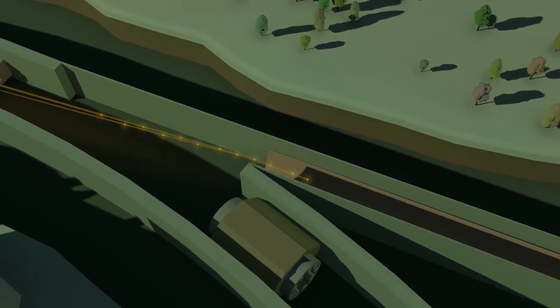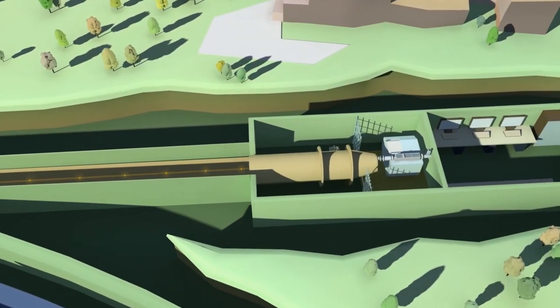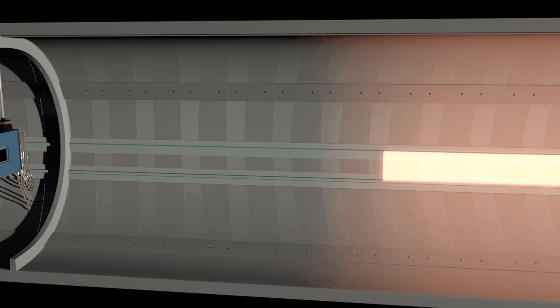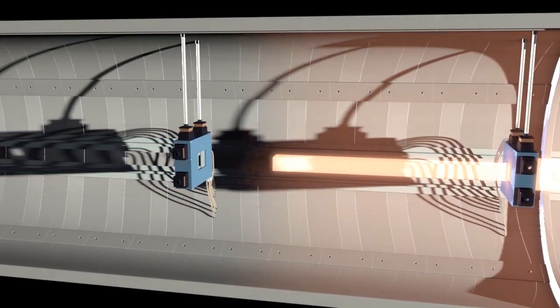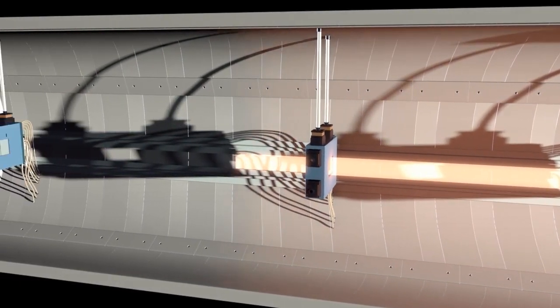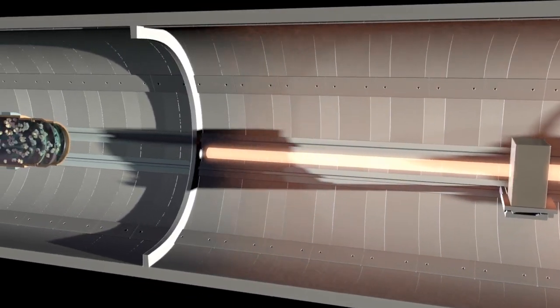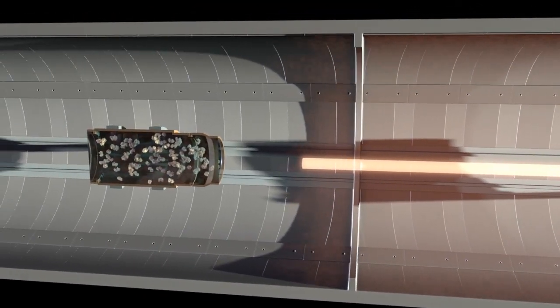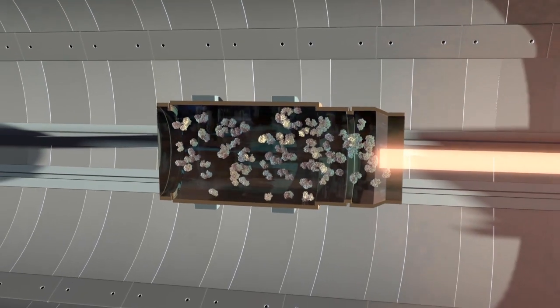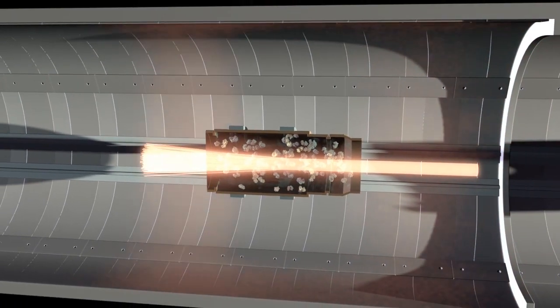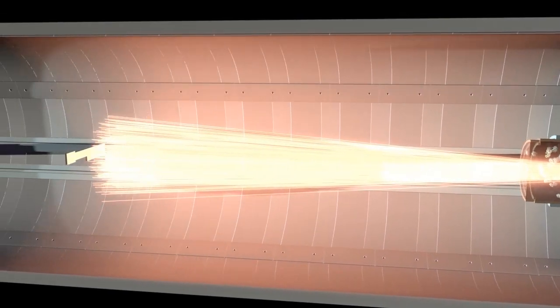These resulting beamlines are then directed towards the sample. But before they hit the sample, the X-ray wavelength is selected by a monochromator and the beam focused by mirrors and shaped by slits. When the sample is hit, most radiation passes through without any interaction and is not of interest. We are only interested in the radiation that scatters off the protein molecules at a small angle, as this contains information about the shapes of the molecules.